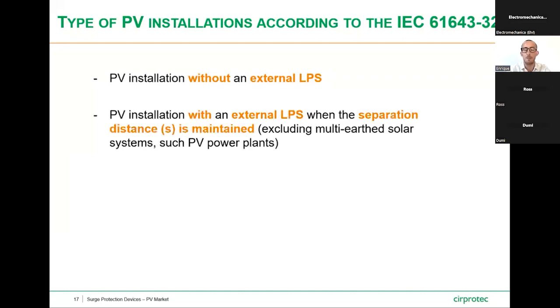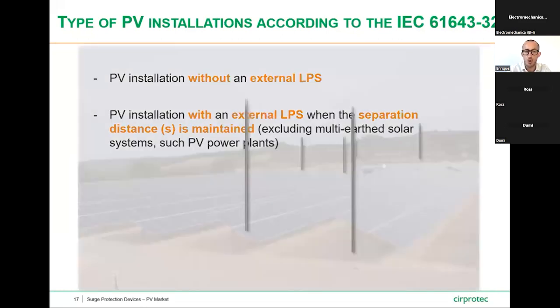Now that we are focused and we understood what should we protect in a PV installation in front of sources, it's time to move on the different type of PV installations according to the IEC, focusing the installation features, the one finished in -32. The first one, there are PV installations without an external LPS. The LPS, let me remind you, that is the lightning rod, the external protection system of the PV installation. Then we do have PV installations with external LPS when the separation distance is maintained. This case is excluding the multi-earth solar systems, such PV power plants.